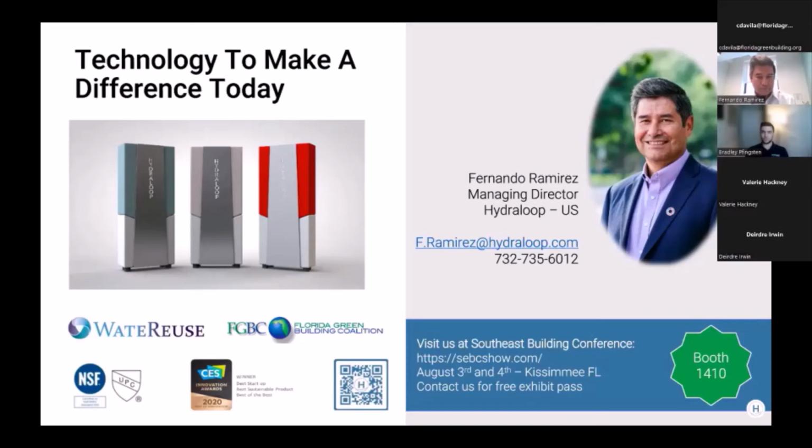Is a lift sump pump to be added to the equipment cost plus the install fee? Can you just clarify that? Yeah, so the pump really depends on what the design of the installation is, right? If we're going to use gravity, if it's on the first floor, we don't need to include one. But if you have a bathroom or something that's in the basement, then we recommend a lift pump. We go through all the diagrams. Whenever a developer has build specs, we review them, we make recommendations, we look at the layout of the piping, and then we make recommendations of what's required for that system to be installed.